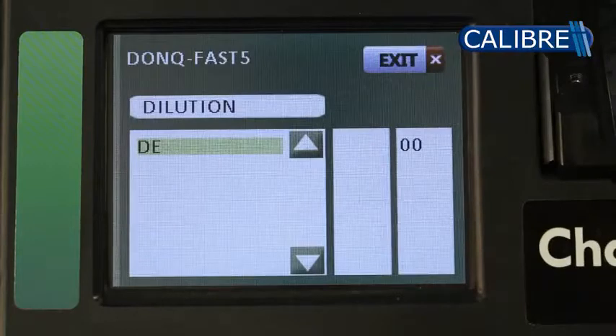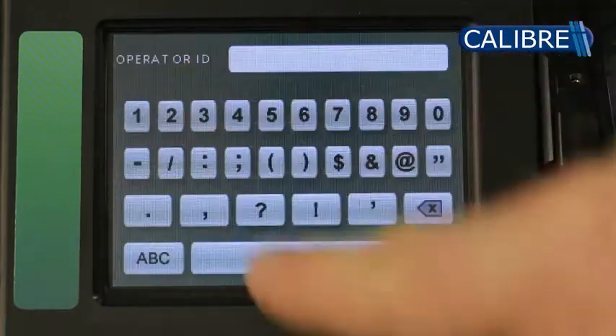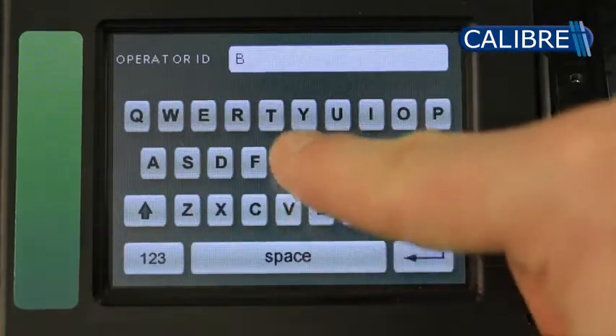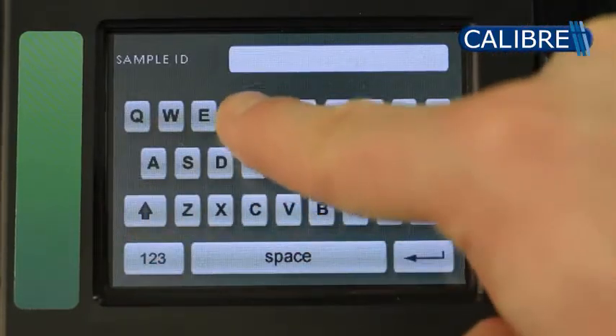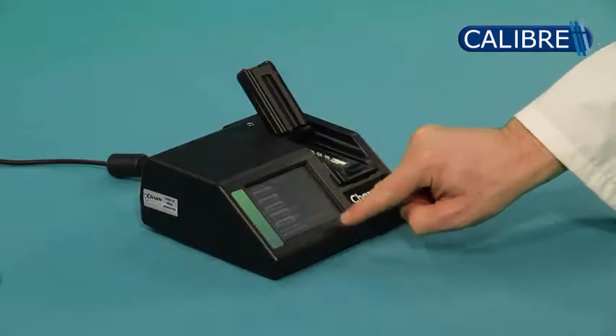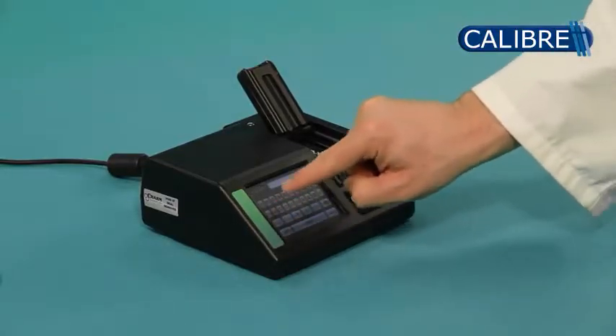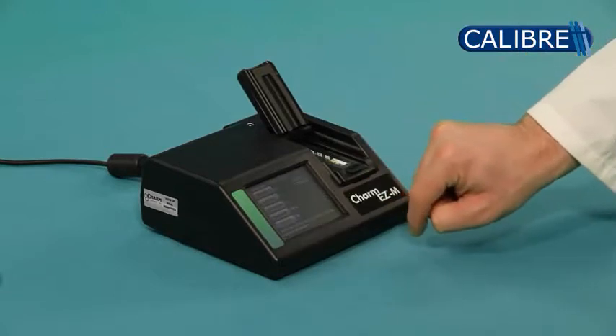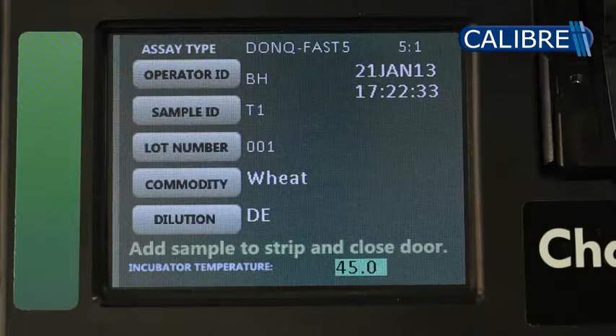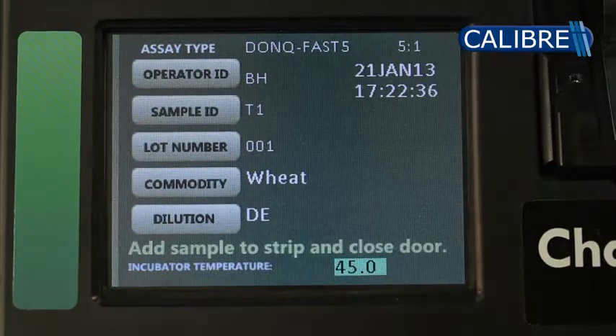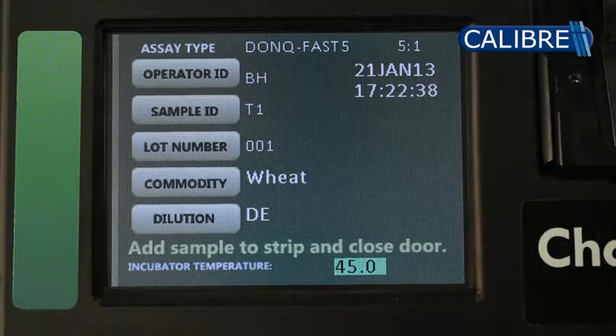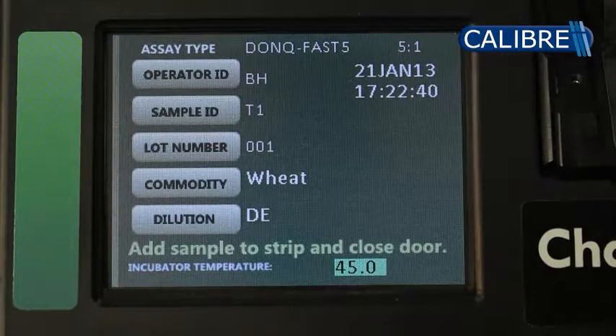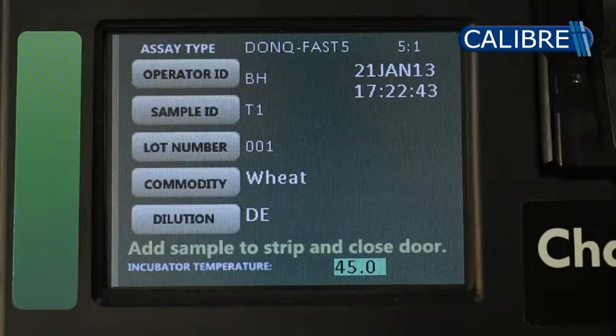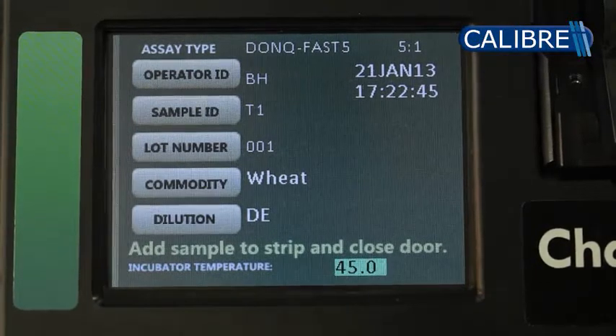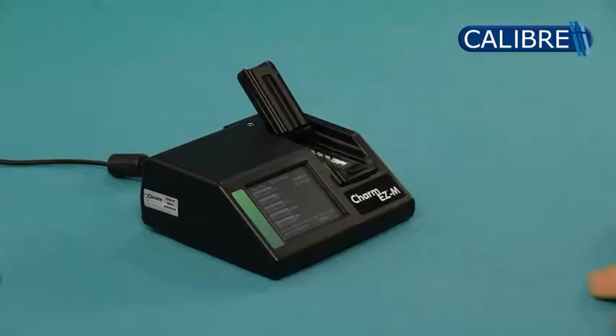First, enter the commodity being tested from the drop-down menu on the screen. You'll then have the opportunity to enter operator ID, sample ID, and lot number at this point, if required. These details can be entered whilst the incubator is reaching the required temperature. Once the incubator has reached the correct temperature, which for this example test is 45 plus or minus 1 degrees centigrade, the test can start. In fact, the reader won't allow the test to continue unless the incubator temperature is correct.